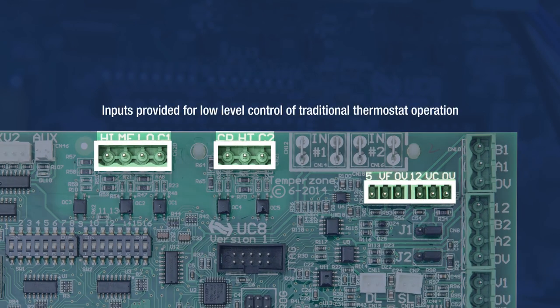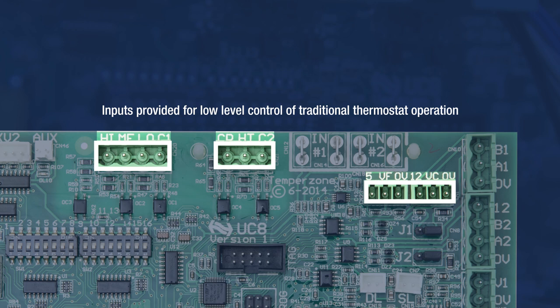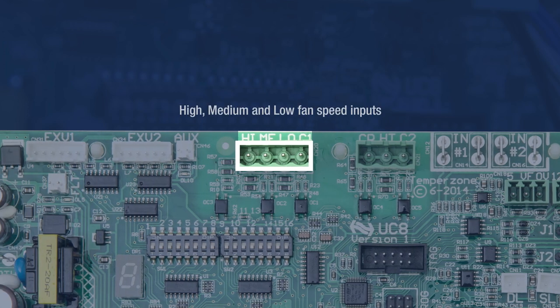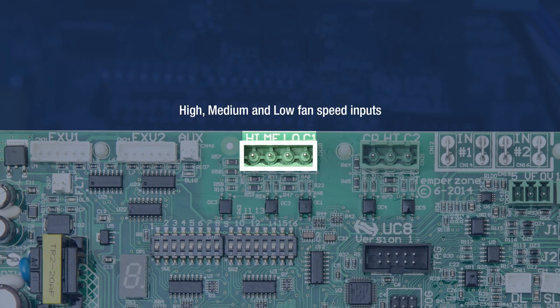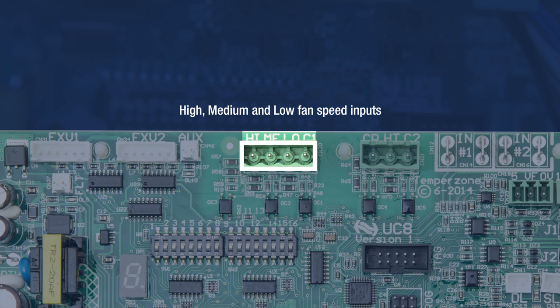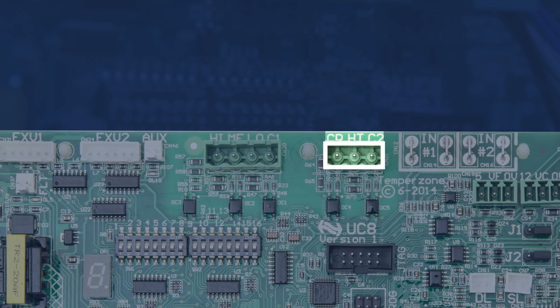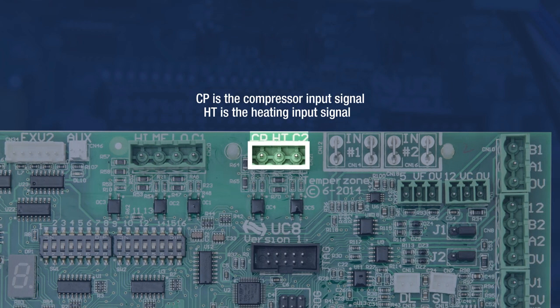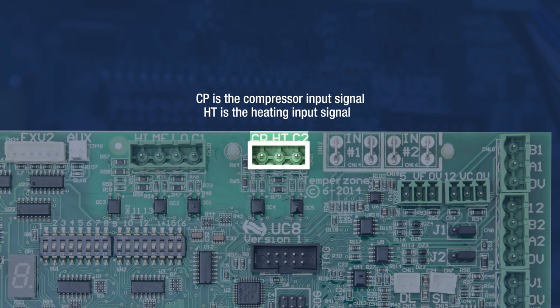HI, ME, LO, CP, HT, VF, and VC are inputs provided for low-level control of traditional thermostat operation. HI, ME, and LO are high, medium, and low fan speed inputs that switch relay coils common to C1. The coils can be operated by 24V AC or 12V DC. CP is the compressor input signal and HT is the heating input signal. Like the fan speed inputs, these terminals are relay coils capable of a 24V AC or 12V DC input and are common to the C2 terminal.